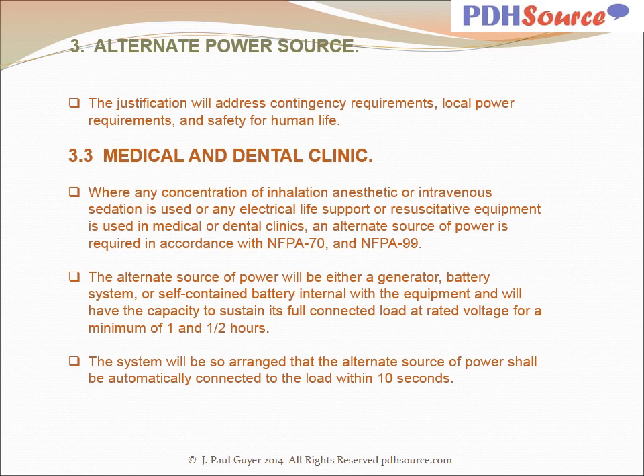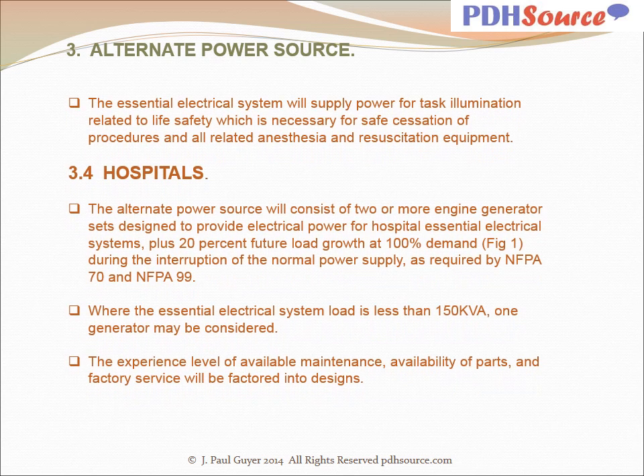The system will be so arranged that the alternative source of power shall be automatically connected to the load within 10 seconds. The essential electrical system will supply power for task illumination related to life safety, which is necessary for safe cessation of procedures and all related anesthesia and resuscitation equipment.